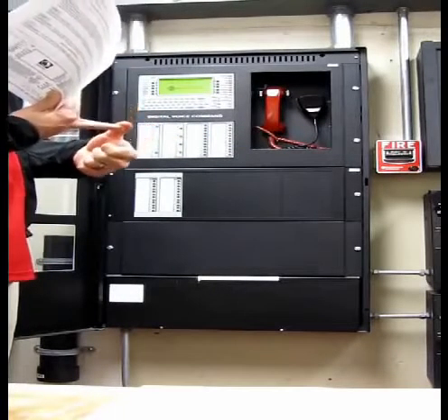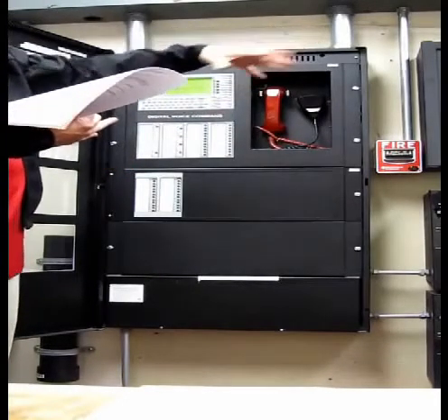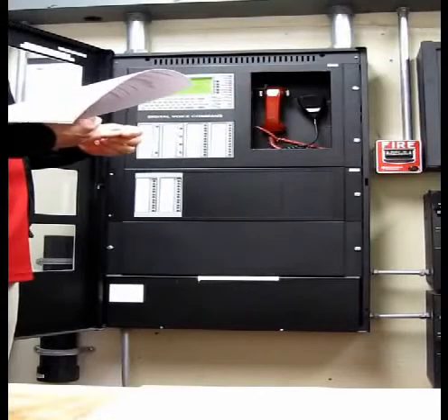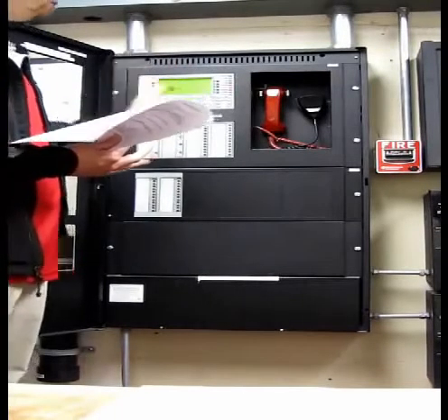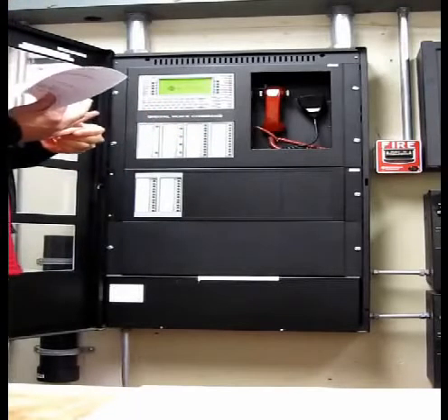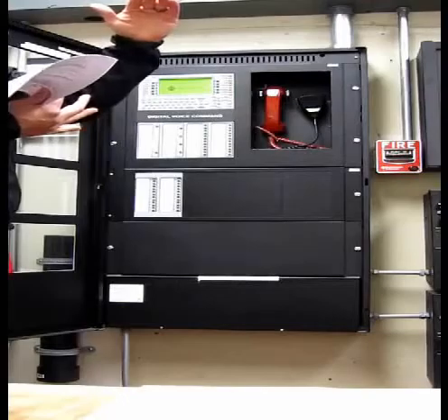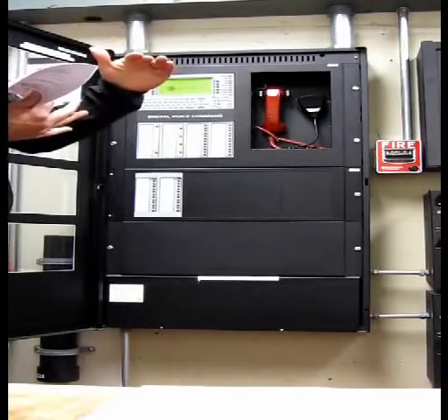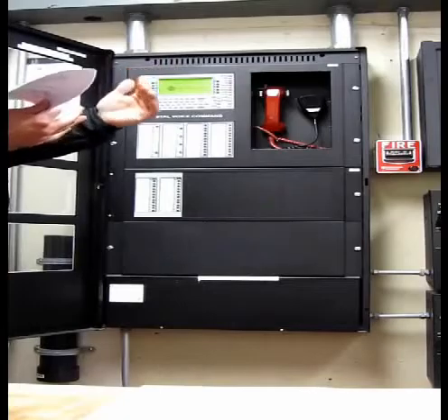Common areas would be the corridors, elevator lobbies, this whole back area you guys have. Any smokes in there are going to cause a full-blown alarm. Now, the way the sequence of operation is set up on this particular system is the alarm that goes off on that floor, it's going to be that floor and the floor above and below that go off only, the audibles and the visuals.